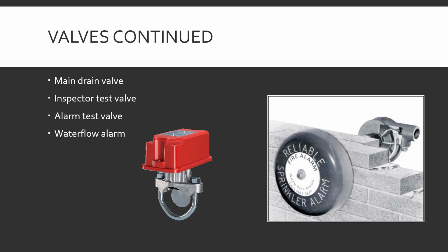Self-explanatory. Inspector test valve. These are smaller valves that are designed to flow when they're open the same amount of water that one activated sprinkler head in the system will give out. So the inspector can gauge the system, get flow rates from the sprinkler heads, and see, all right, everything's how it should be. There's no drastic change. The water supply to the building hasn't changed. We're not suddenly getting 50 gallons per minute less, or some big number. Everything is where it should be.